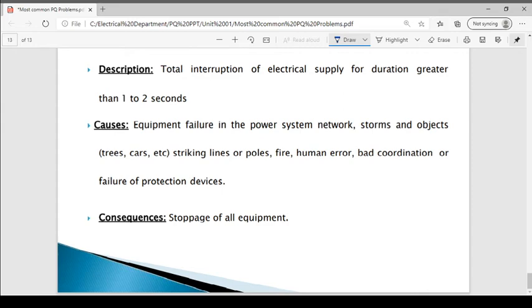So what are the symptoms of poor power quality? How will you find out that the quality of the power has deteriorated? We could enlist certain symptoms. Power quality problems will result in a circuit breaker tripping without being overloaded, equipment failures due to thunderstorms, automated systems stopping and restarting for no apparent reason, electronic systems failing to operate on a frequent basis, and equipment failing at the same time.